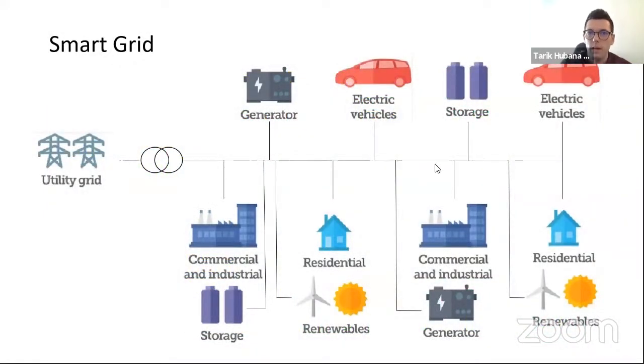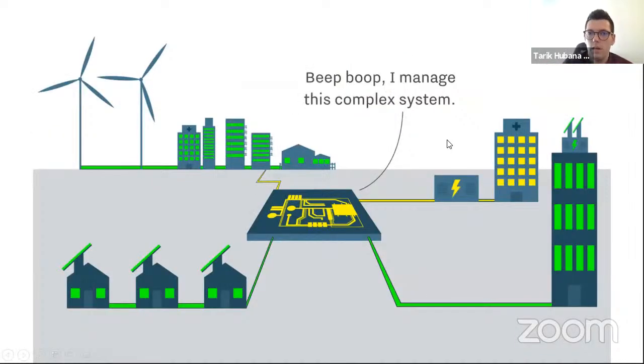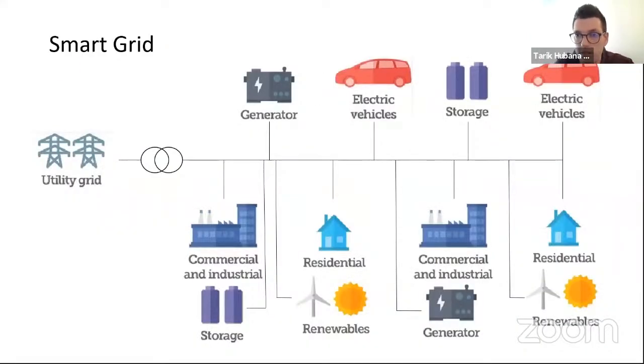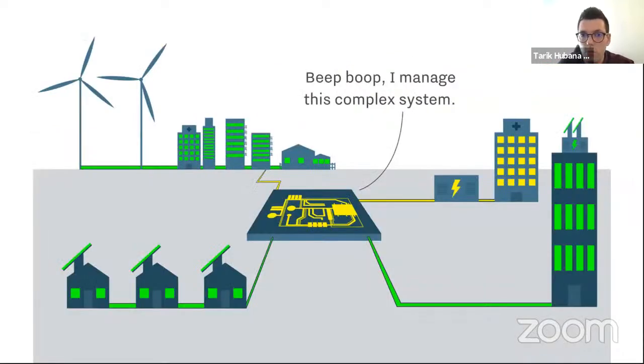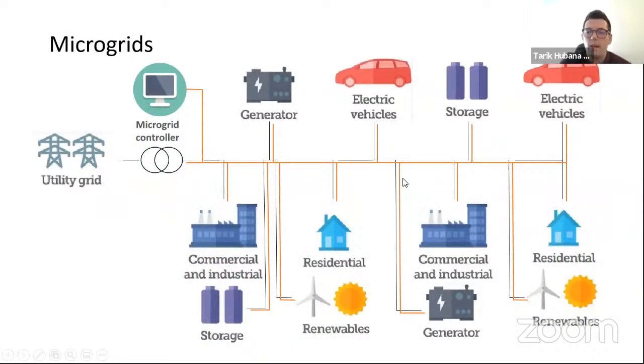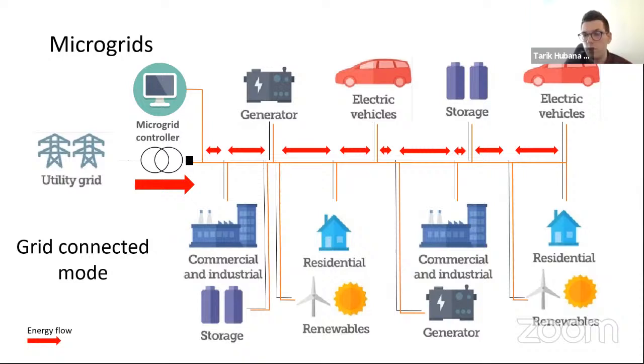So now let's go back to the smart grid that we explained earlier. In order to control all of these different entities in the microgrid, we need to have a microgrid controller. So see, here we have this microprocessor-based electronic device that has a large number of inputs and controls these different entities within the microgrid. With this type of control, the grid can switch between grid connected mode and islanded mode of operation. So here we see the grid connected mode, where the energy is supplied from the utility grid. In the scenario where we have enough energy within the microgrid, we can go into the islanded mode of operation.